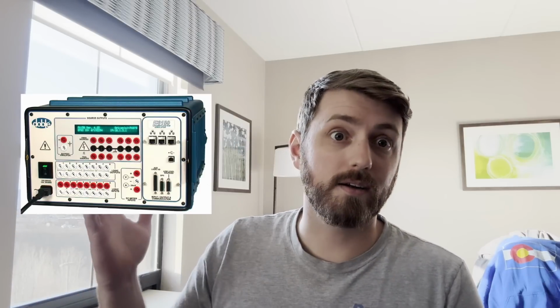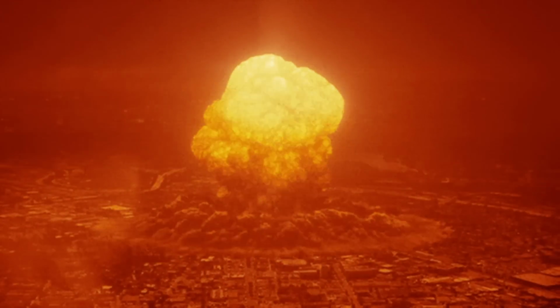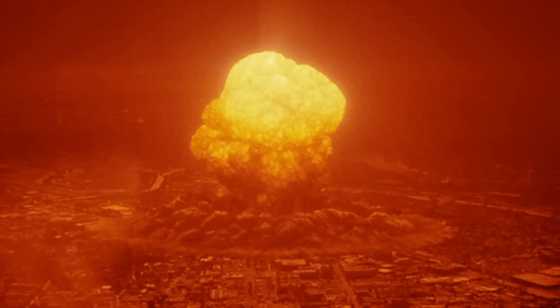So he walks around behind the end of the gear, turns on the DC battery bank breaker, and immediately backfeeds the battery sim output on my Doble F6150 with 125 DC from the station batteries. It lets all the magic smoke out. It doesn't work at all. There was a mushroom cloud. I had people from 6 blocks away coming over to ask what happened. It was a nightmare, so much smoke came out, it was incredible.